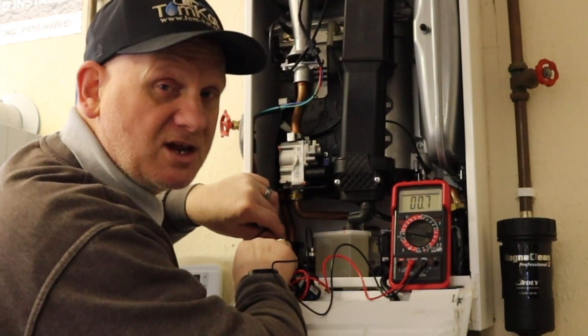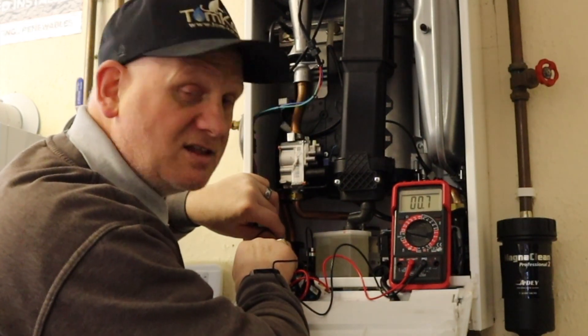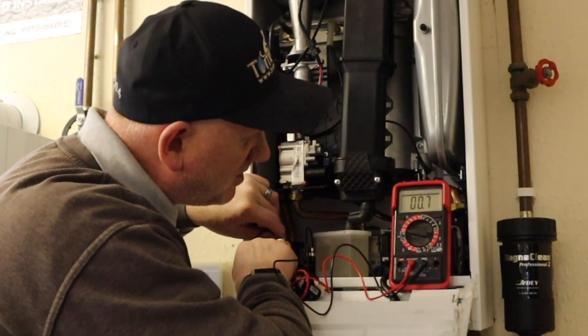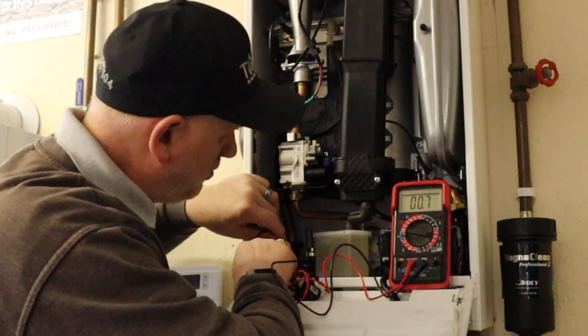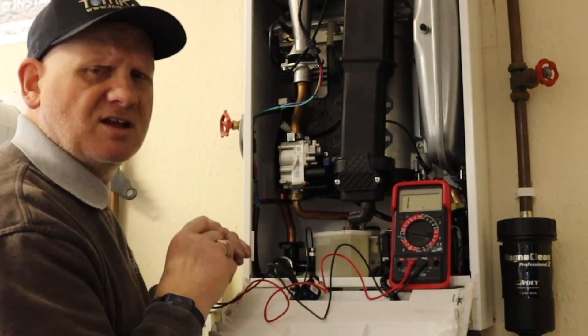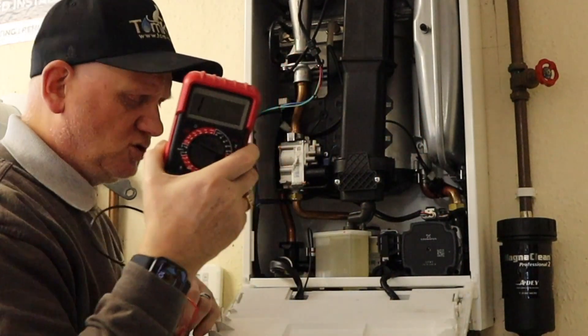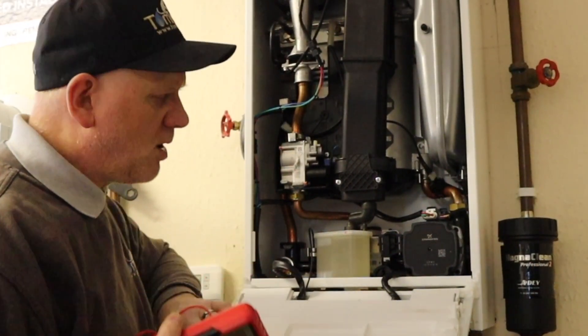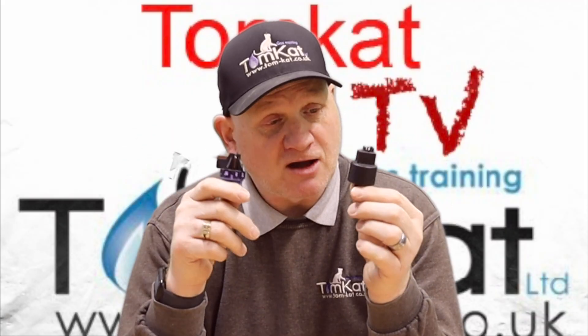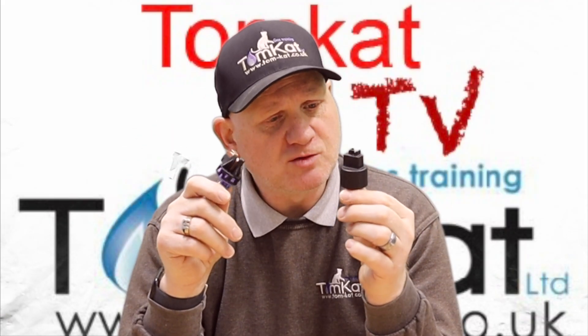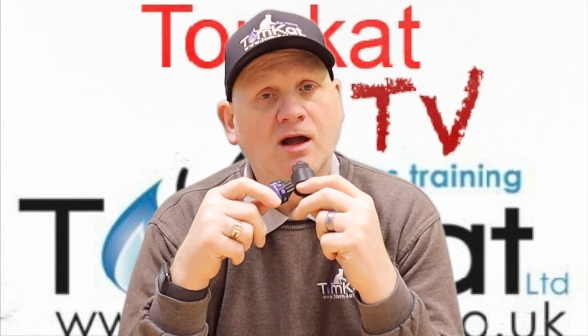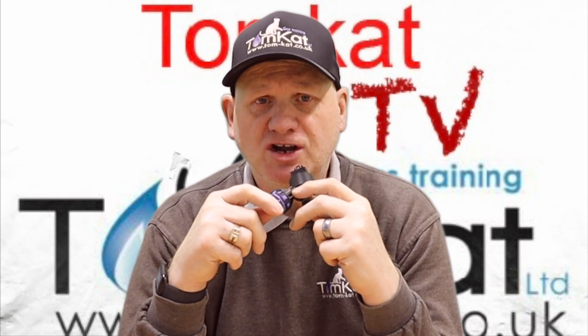There you go, we're getting a reading because the pressure is making the contact and we're reading 0.7 ohms. So that is telling the boiler that there's water in there. Let's see what pressure's in it. Should be around 1 bar, and it is just over 1 bar. Now that's how these two little devices work and how you test them. Hopefully you've liked this video and I'll catch you on the next one. Cheers.